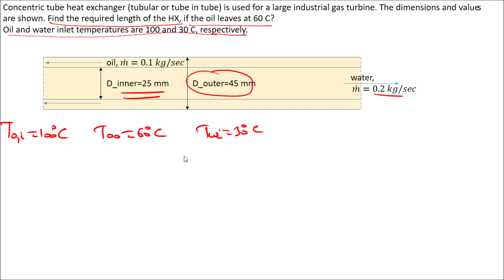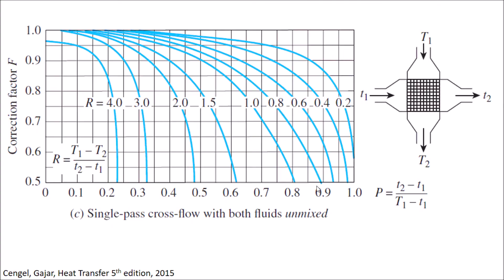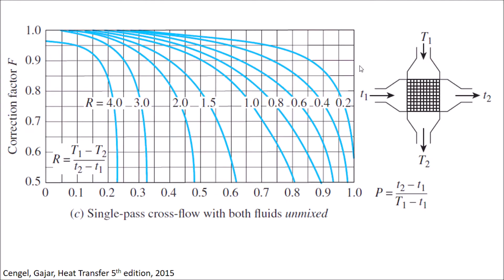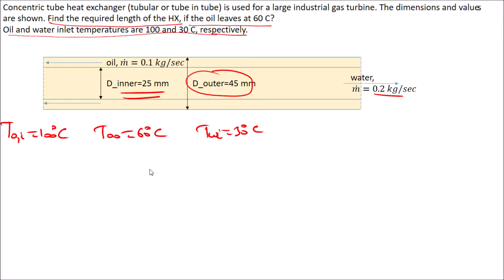This is a sizing problem. For sizing problems we use specific equations. If it is a temperature or rating problem, different relations apply. The unknown here is the water outlet temperature, which we will find first. Then we will use Q = U·A·F·LMTD. F is one, and from the area we will get the length of the heat exchanger.